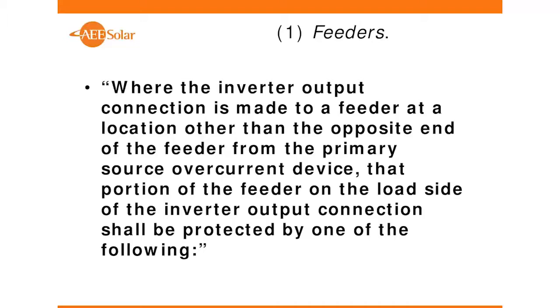All right? So it says where the inverter output connection is made to a feeder at a location other than the opposite end of the feeder. So what we're saying is that we've got a feeder starting at the main panel going to a sub-panel. Somewhere in the middle, and we'll show some pictures of this, we're going to interject a PV system. Then we have to address some problems that we've created by putting extra power in the middle of that circuit. Now, when it's at the opposite end, what happens?